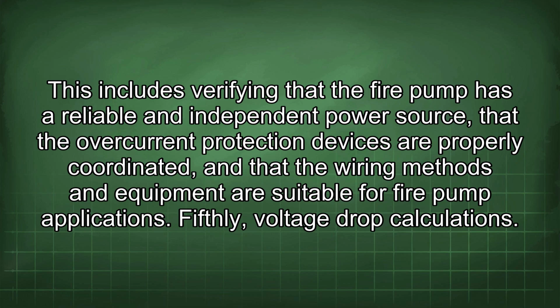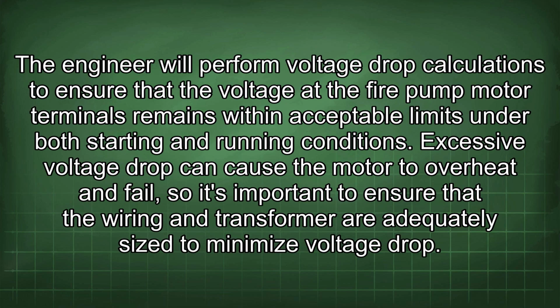Fifthly, voltage drop calculations. The engineer will perform voltage drop calculations to ensure that the voltage at the fire pump motor terminals remains within acceptable limits under both starting and running conditions. Excessive voltage drop can cause the motor to overheat and fail, so it's important to ensure that the wiring and transformer are adequately sized to minimize voltage drop.